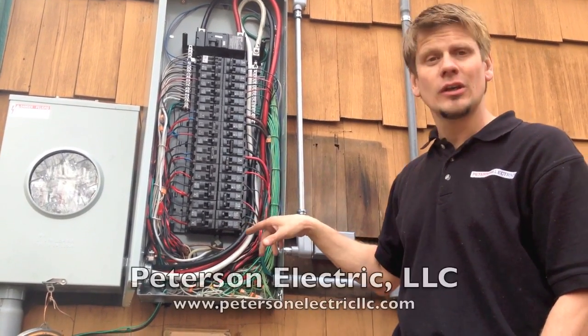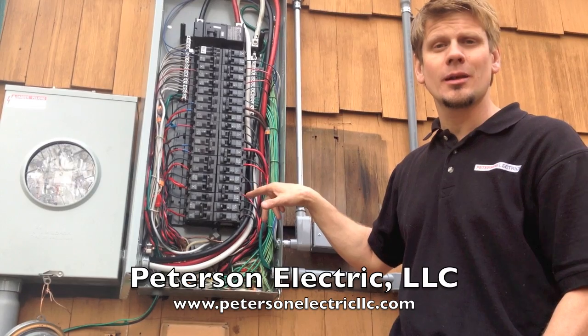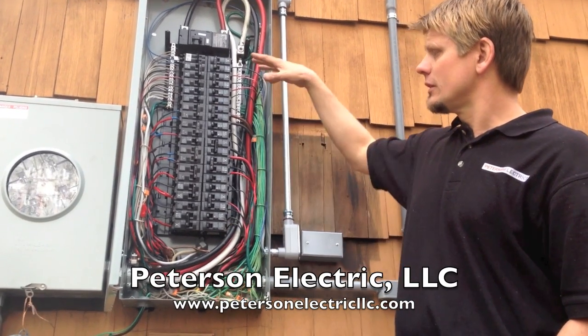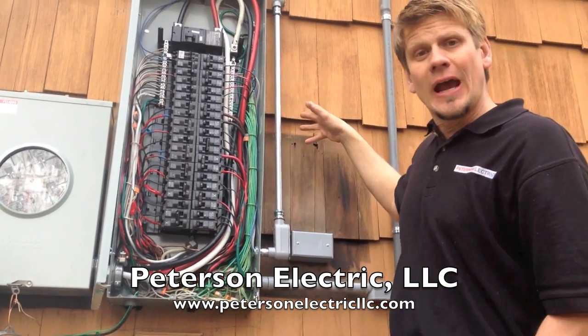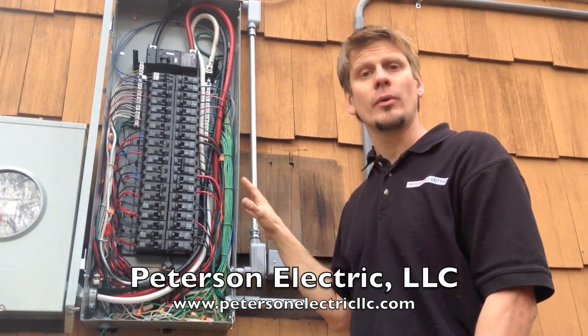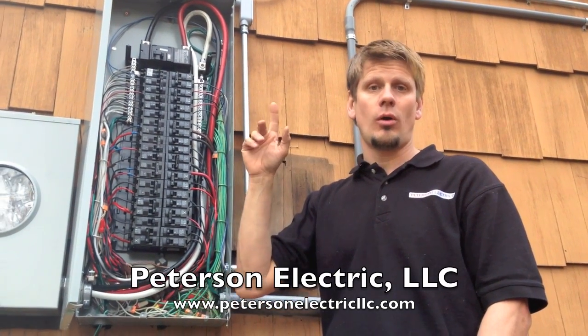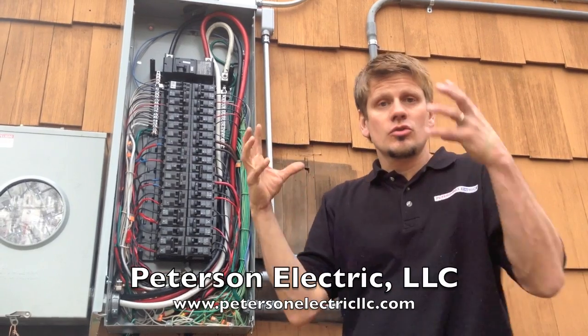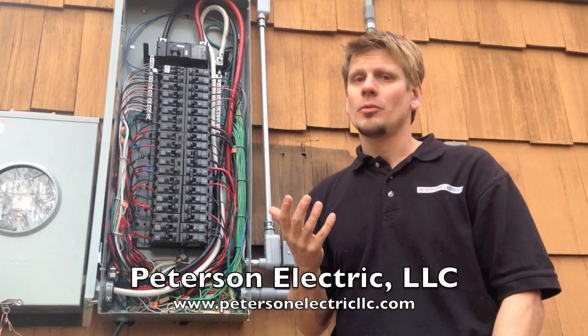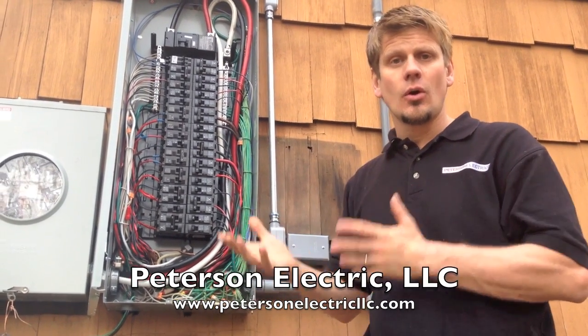In this case, with these kind of breakers, it might have been $1,000 just for the breakers because we had a lot of two-pole 20-amp breakers for the baseboard heaters. And if you end up arc faulting the circuits inside and they're tied together, now you're dealing with more time and material to get those separated. In this particular house we had found some splices in the drywall, and some of the circuits were just tied together in one box — stuff like that is impossible to find. So I don't know how they're going to amend that for the new code if they decide to go this way.